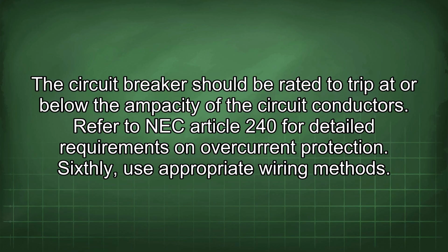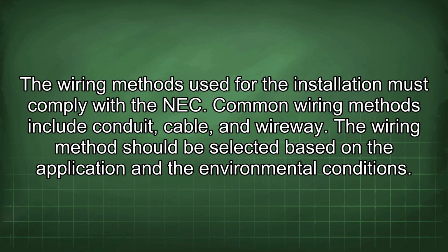Sixthly, use appropriate wiring methods. The wiring methods used for the installation must comply with the NEC. Common wiring methods include conduit, cable, and wireway. The wiring method should be selected based on the application and the environmental conditions.